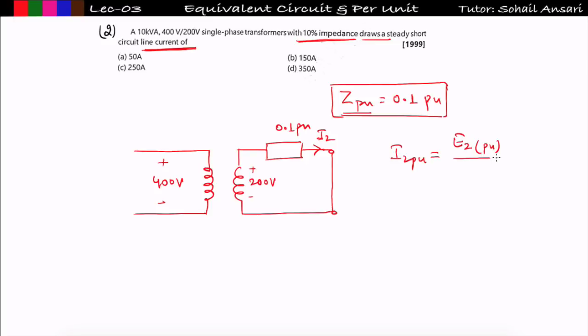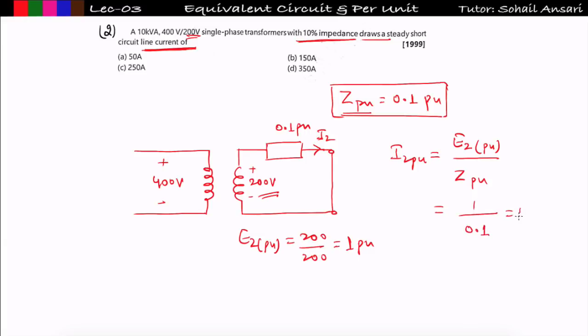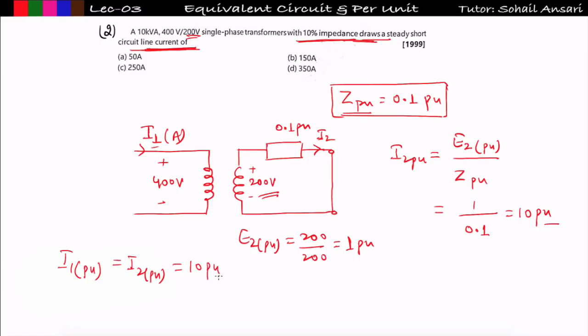Draw the transformer with Z_PU represented on the secondary side as 0.1 per unit. Primary voltage is 400V and secondary is 200V. Short circuiting the secondary terminal, we find I₂ in per unit: E₂ in per unit = 200/200 = 1 per unit. So I₂ per unit = 1 / 0.1 = 10 per unit. Since per unit parameters are equal in primary and secondary, I₁ per unit also equals 10 per unit.